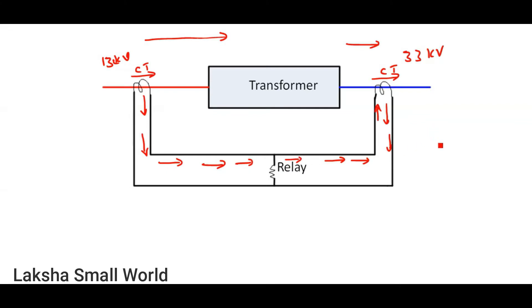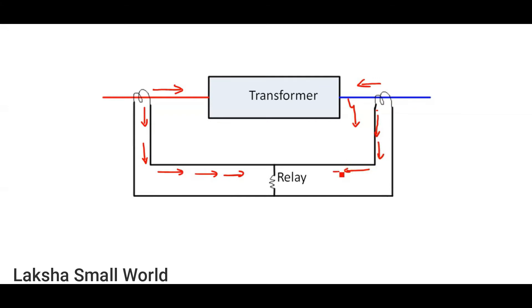In case there is any fault within the transformer, the current direction will reverse. Current will then flow in the opposite direction on the HV and LV sides, so the direction of current in the relay changes and current flows through the relay. The relay will then operate and give a trip signal to the circuit breaker. The circuit breaker will open the circuit and the transformer is safe.